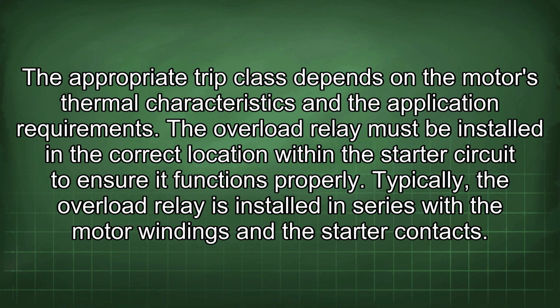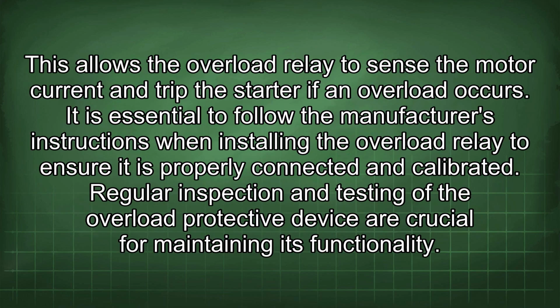The overload relay must be installed in the correct location within the starter circuit to ensure it functions properly. Typically, the overload relay is installed in series with the motor windings and the starter contact. This allows the overload relay to sense the motor current and trip the starter if an overload occurs. It is essential to follow the manufacturer's instructions when installing the overload relay to ensure it is properly connected and calibrated.